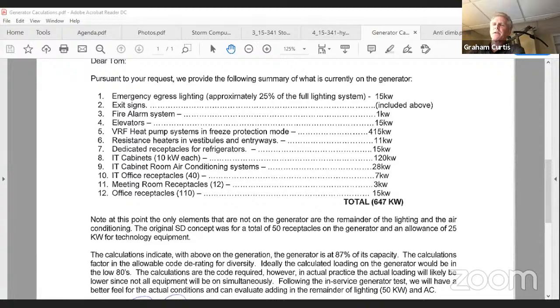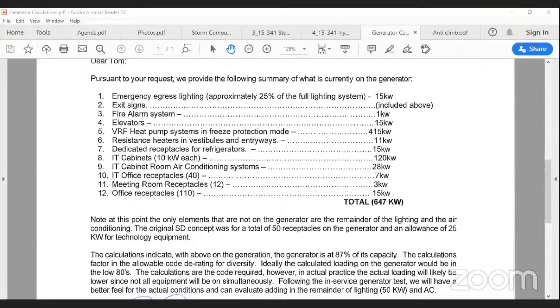Okay, so the duration that you can run the generator will be less than this, this is like the startup. Right, so my point being, I understand you have to calculate somehow, but in the reality of operation, if the building is operating, everything is drawing as it normally does, and ambient temperature is, let's say 65 to 70 degrees, whatever that night might be, and there's a power outage, the unit is not starting from a dead start sub-zero mode, it already has ambient temperature that it's moving around. Am I oversimplifying that, or is that factually correct, Graham?